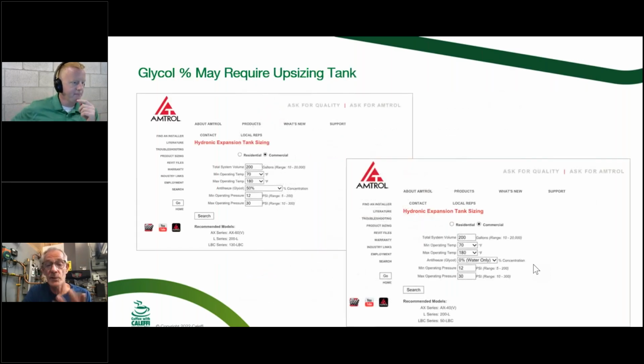So you'll see on this one here, I put 50% glycol. And I don't know if you recognize those tanks, but the tank size went up quite a bit by just adding glycol to that same system with the same temperature and pressure criteria. So I'm not a big fan of glycol unless you have freeze protection. It brings a lot of baggage. Your expansion tank and your pump sizing change. It's really tough to get air out of glycol.